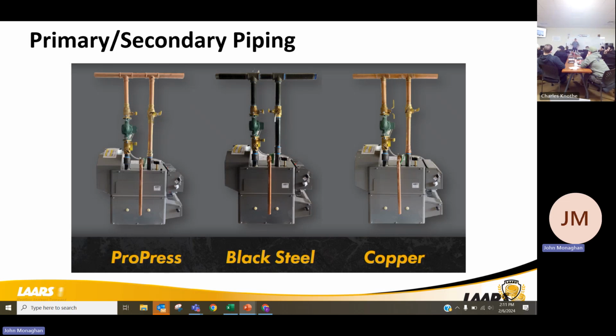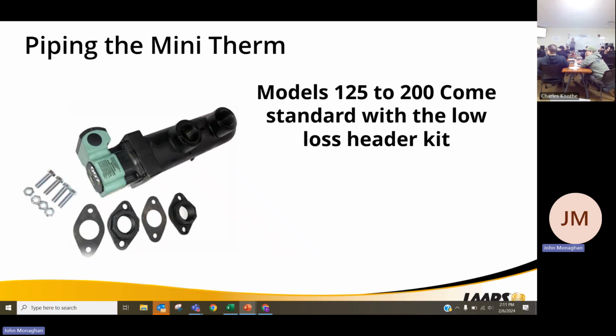So on the 125 and up, you have a built-in low loss header, connecting the heat exchanger, and you're going to pipe this series pipe, not parallel, not secondary. Pump it. Okay. The smaller sizes, accessory.